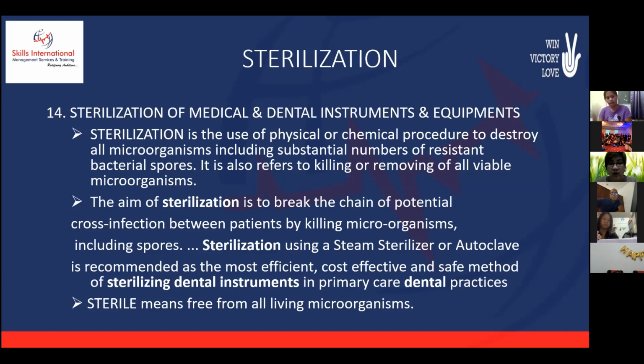So it is recommended as most efficient, cost-effective, and safe method of sterilizing, especially for the dental instruments in a primary care dental practices. Mostly, ang ginagamit dito sa sterilizers, yung mga operating room instruments, yung ginagamit talaga ng doktor during surgery, and yung mga dental care centers.